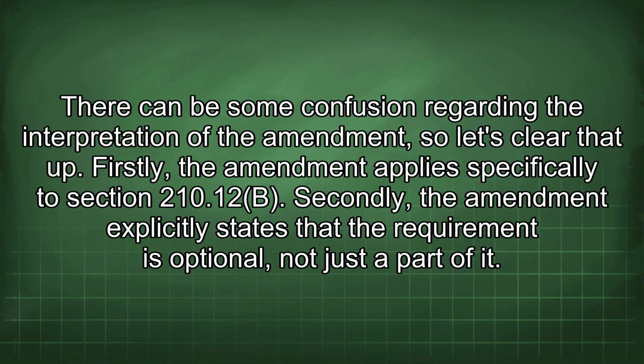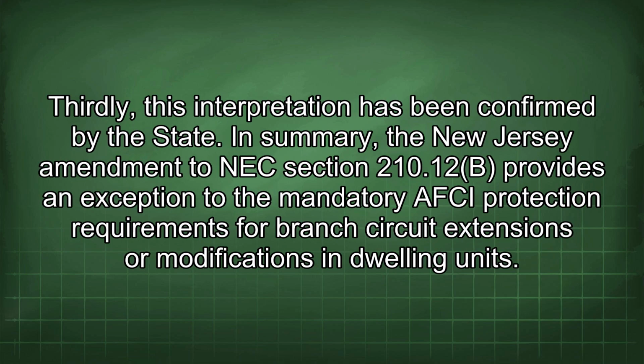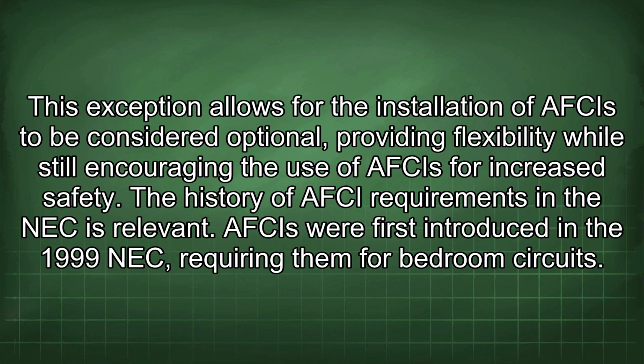There can be some confusion regarding the interpretation of the amendment, so let's clear that up. Firstly, the amendment applies specifically to Section 210.12(B). Secondly, the amendment explicitly states that the requirement is optional, not just a part of it. Thirdly, this interpretation has been confirmed by the state. In summary, the New Jersey Amendment to NEC Section 210.12(B) provides an exception to the mandatory AFCI protection requirements for branch circuit extensions or modifications in dwelling units. This exception allows for the installation of AFCIs to be considered optional, providing flexibility while still encouraging the use of AFCIs for increased safety.